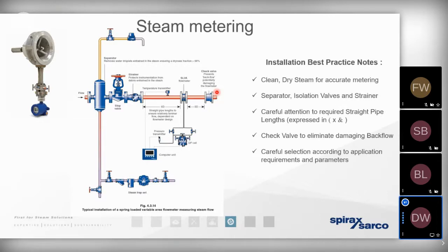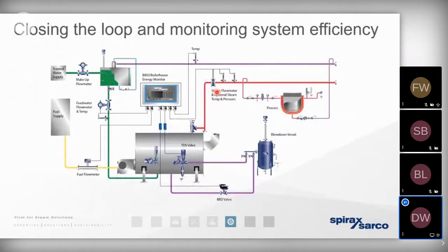But we can also take the steam meters one step further. For example, if we've got a number of different meters in the boiler house that are sending a signal to a boiler house energy monitor, then we can get a true understanding of the actual steam distribution efficiency. Let's say we've got a raw water makeup meter. Let's say we've got a fuel meter. We could have a meter between the feed tank and the boiler, and we could be metering the steam that's going out to the various processes.